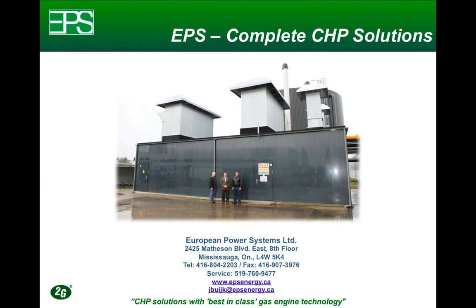The next question: for heat recovery, do you use condensing heat economizers, which are much more efficient? We do, at certain sites. Most sites will cool the exhaust to 120 degrees Celsius. We also have applications where the exhaust is cooled to 50 degrees Celsius, and it really depends on how much of that lower temperature heat can be utilized. But the answer is yes, we do use condensing heat recovery as well.